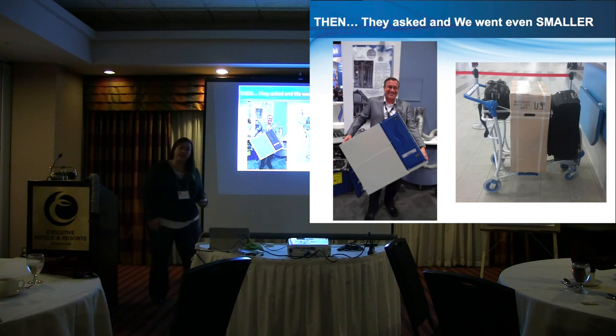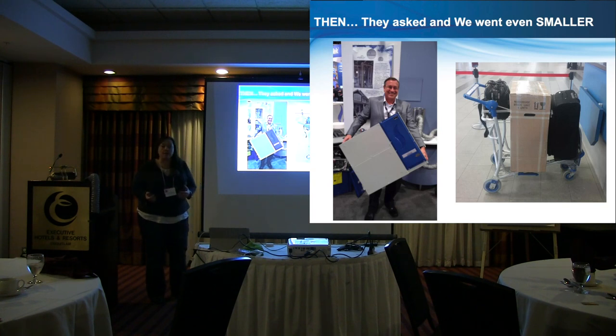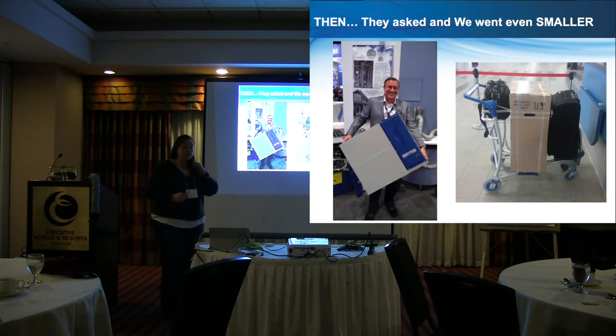So then utilities said, okay, now we've got diversification into even smaller units, multi-res construction, and we're absolutely out of the market when it comes to gas, right? So you guys that rep heat pumps and combi systems, everything else, gas is really taking a hit when it comes to even smaller units, because you can't get equipment small enough. So four-stage gas systems are completely out of the equation. So they asked us to go smaller and we did. Have you guys seen any of these? Cam, you've seen them? So this unit's 62 pounds fully loaded.